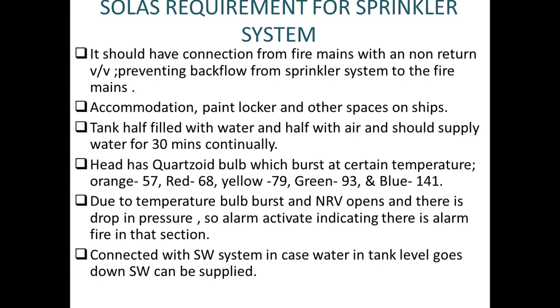So we have this system available in accommodation, paint locker and other spaces on ships. The tank is half filled with water and half filled with air, and should supply water for 30 minutes continuously. It should be designed so that it is able to supply water for 30 minutes continuously.